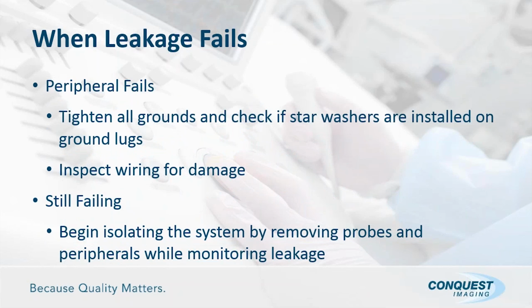What about peripherals? What happens when peripherals fail? Well, the first thing, you can check all grounds and see if star washers are installed on ground lugs and inspect wiring for damage. Same thing we talked about earlier. One thing I'd like to point out while we're talking about this is peripherals can cause an unusual condition while doing electrical safety if they're not connected to the ultrasound system in a correct manner.